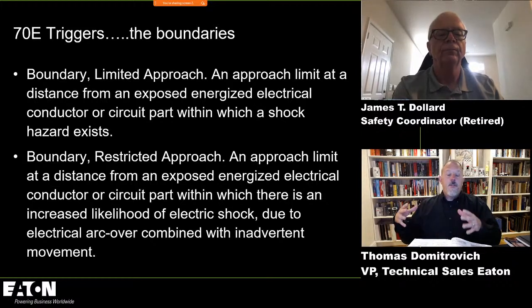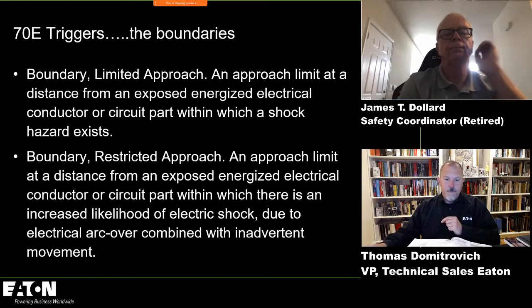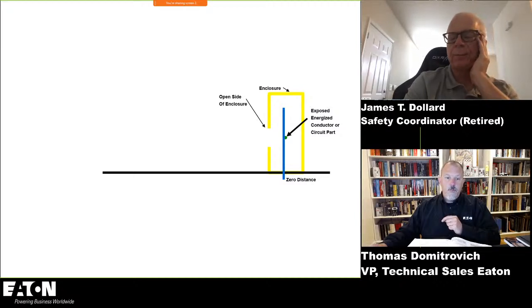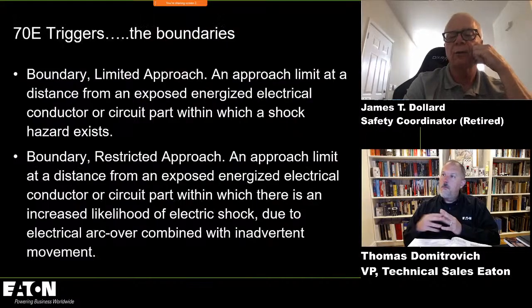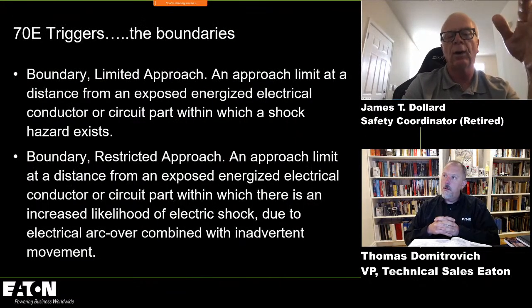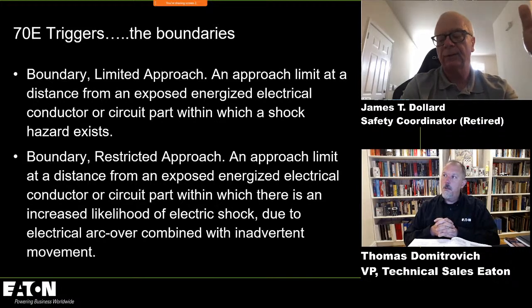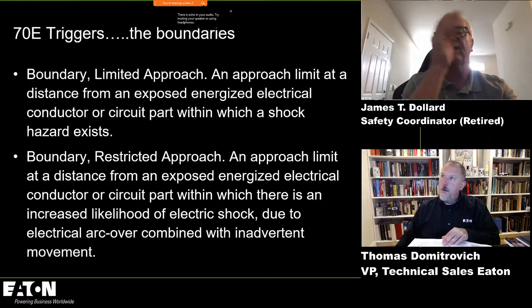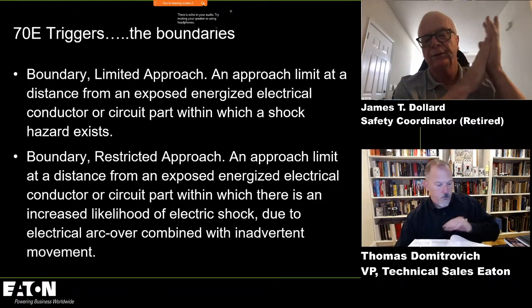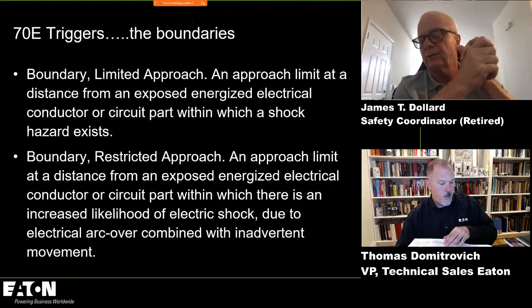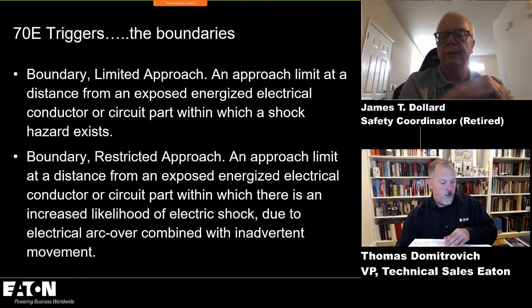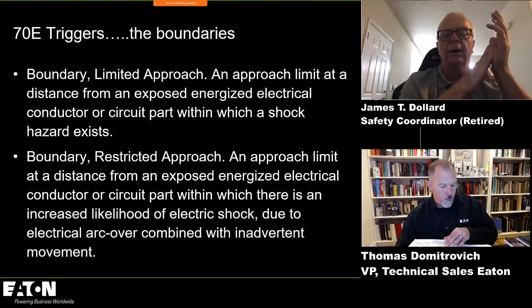Then we have the boundaries. So you have your limited approach, and actually I have a diagram on that one. The key is that the boundaries are the triggers. The limited approach boundary is at a limit where there is a shock hazard. That starts at 50 and goes to 750 volts AC. It'll be 3'6". And we're saying there that there is a shock hazard because you could lean into it, or something you're holding could go into it.